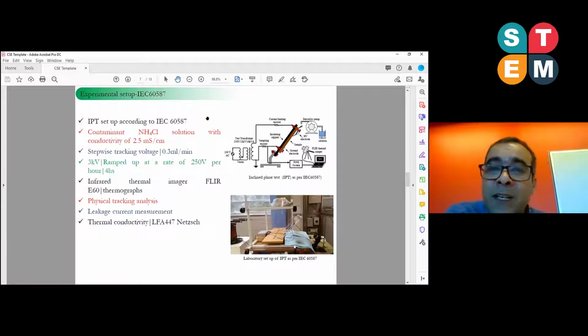This is the experimental setup according to 60587. In 60587, we have to mount the samples on an insulating support. That is the insulating sample here. Second, we have to apply the high voltage with a test transformer. How much high voltage we apply and what the flow rate of the contamination solution is are defined in the standard. So we have to follow all the instructions according to the standard.